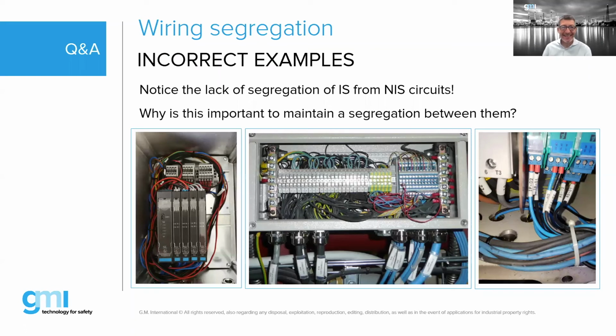There you go. So if you look at the picture on the right-hand side, if you notice, there's a plastic partition coming down, and you see that there's some output from those various barriers going via barrier glands into the field devices. These are mounted inside of an EXD box. And then obviously there's some sort of electrical device on the left-hand side, and that's powered. Now that partition there is to meet that 50 millimeter requirement. However, the problem is that they looped those cables and they dropped them down through the entries. So therefore we missed out our 50 mil segregation between the cables.